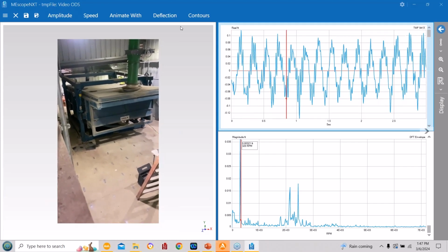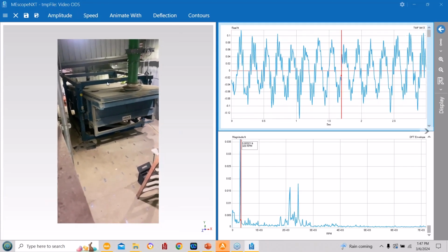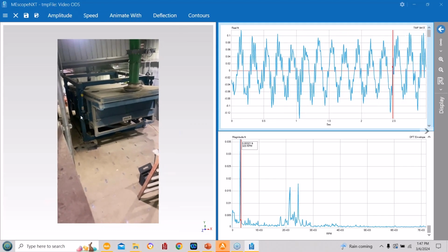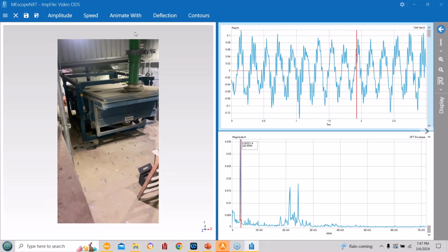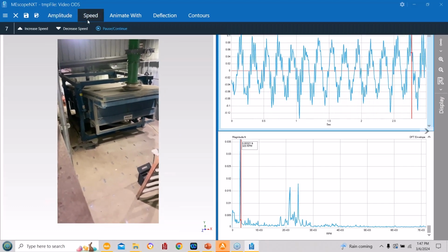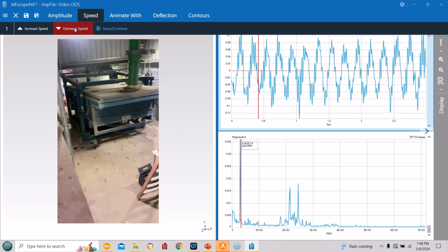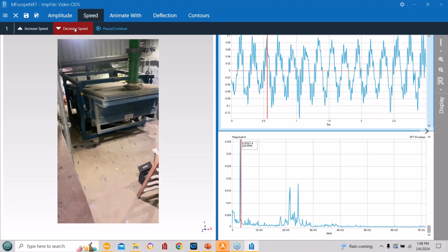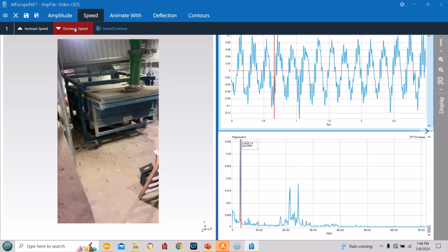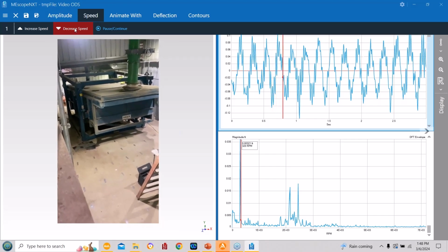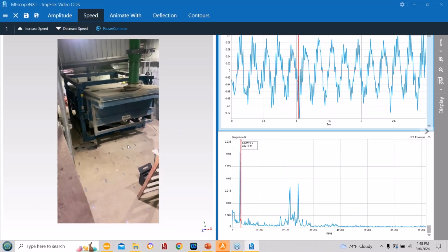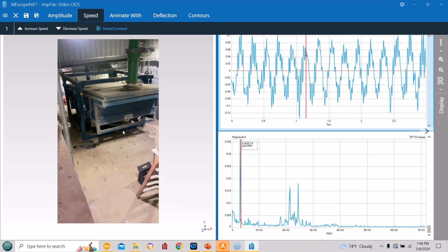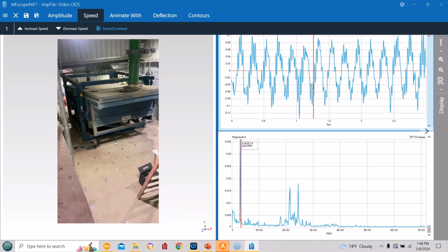Which is like the whole building is moving, which it is. The frame was not twisting like this. This is like some overlap processing that is going, plus the frame's moving really fast. So speed decrease. And you remember what those beams were doing down below. This thing is moving in the axial direction of the machine, and it's pitching as well.